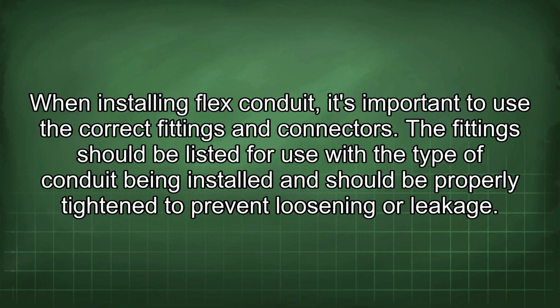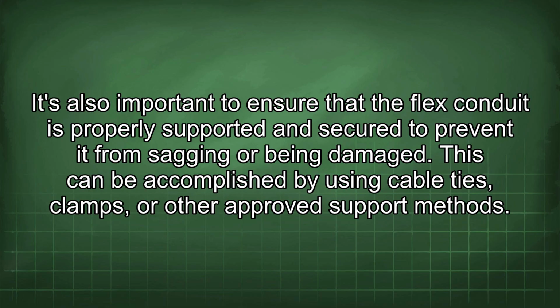The fittings should be listed for use with the type of conduit being installed and should be properly tightened to prevent loosening or leakage. It's also important to ensure that the flex conduit is properly supported and secured to prevent it from sagging or being damaged. This can be accomplished by using cable ties, clamps, or other approved support methods.